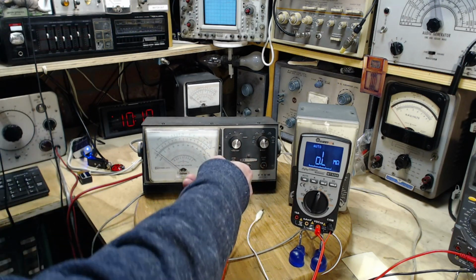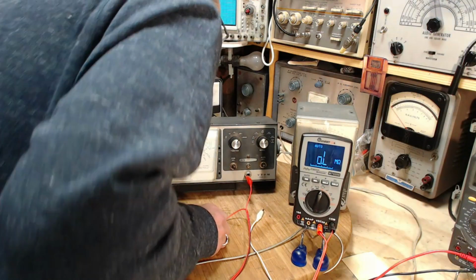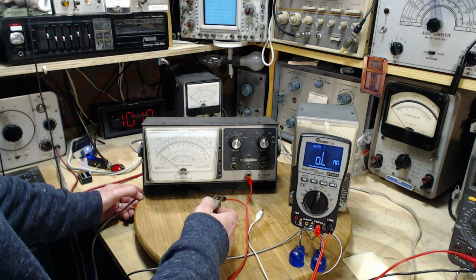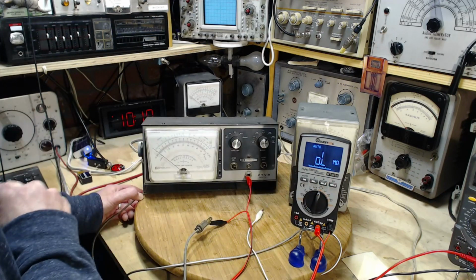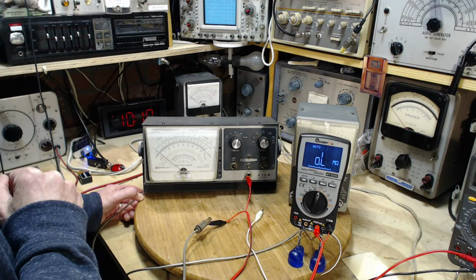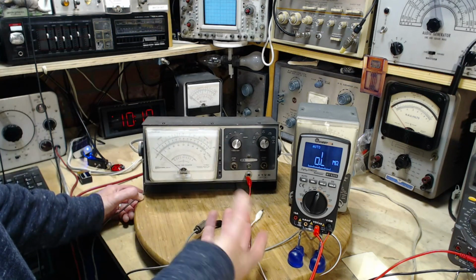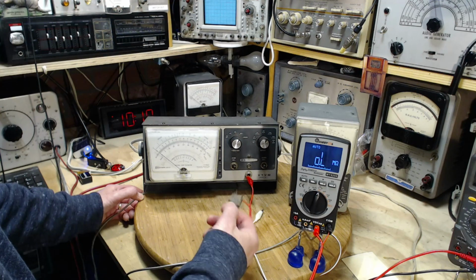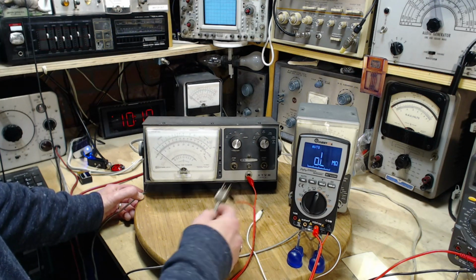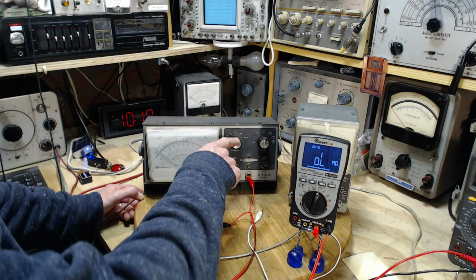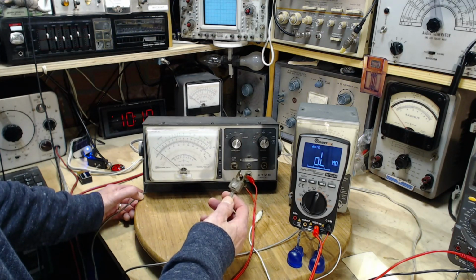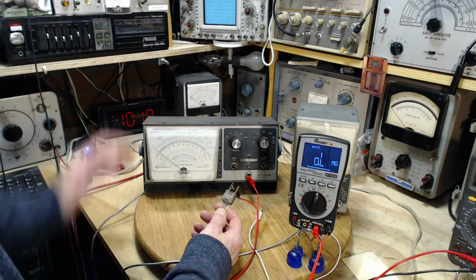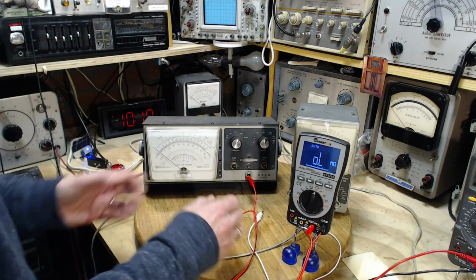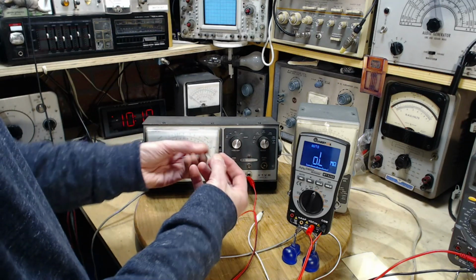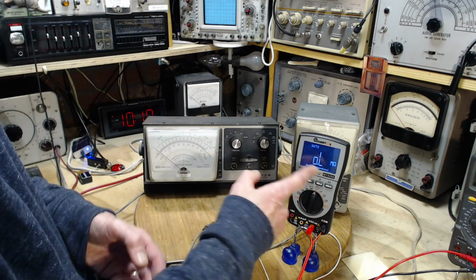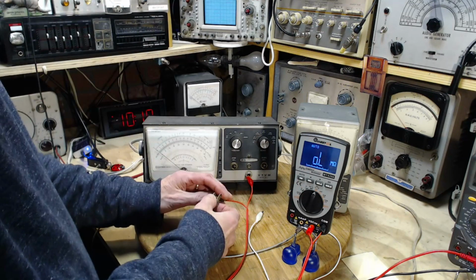Am I using the right unit here? Yeah. I'm a little surprised at that. I kind of thought we would see something. It's megohms. That's pretty reassuring. So I'm just looking for a leak, basically, between the power transformer primary, which is where, wait a minute. This is switched on, so we're okay. Yeah. The primary and the cabinet, and there appears to be nothing. So this means when I'm getting these low voltages, they may be traveling through a resistance that's, what, more than this meter can read? I'm not sure about that.